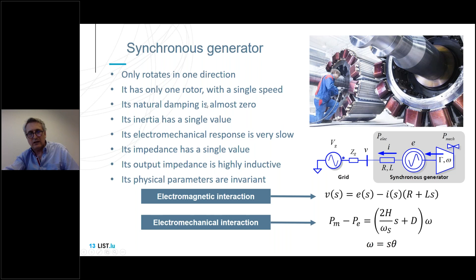When we talk about stability, you can see here the response of a synchronous generator with a given inertia and damping. You have a stable response in the beginning. This would be an insufficient damping torque. There is not enough damping torque and there is an oscillation because something was connected or some line tripped at a given time, and this is the regular undamped, or unstable, response of the frequency of the angle oscillation. The synchronous generator doesn't have enough synchronizing torque, and in a couple of swing cycles it is directly disconnected. It usually happens after a strong fault, for example, a short circuit close to the terminals.